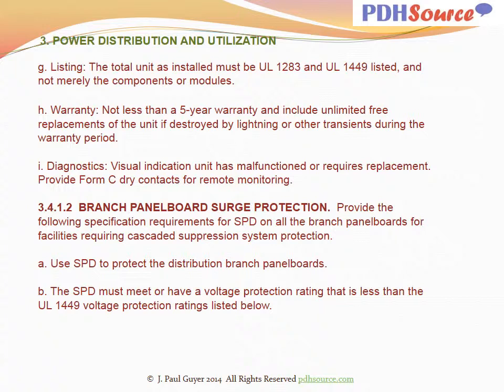The total unit as installed must be UL1283 and UL1449 listed, and not merely the components or modules. Not less than a 5-year warranty, and include unlimited free replacements of the unit if destroyed by lightning or other transients during the warranty period. Visual indication if the unit has malfunctioned or requires replacement, and provide Form C dry contacts for remote monitoring.